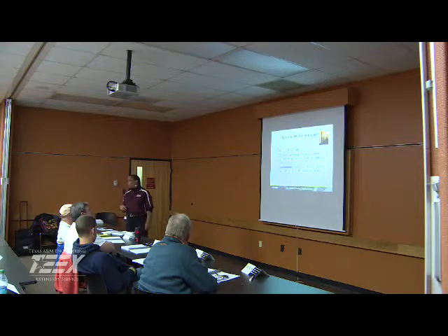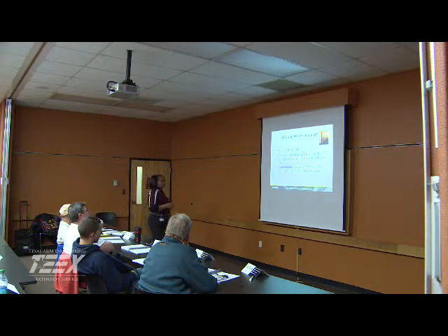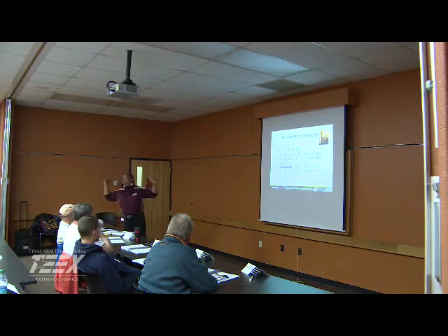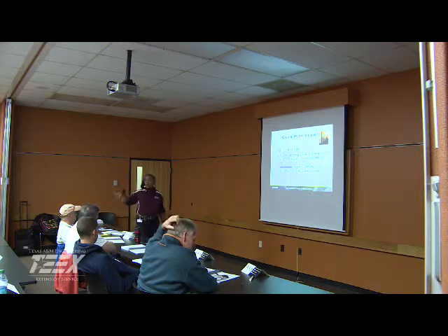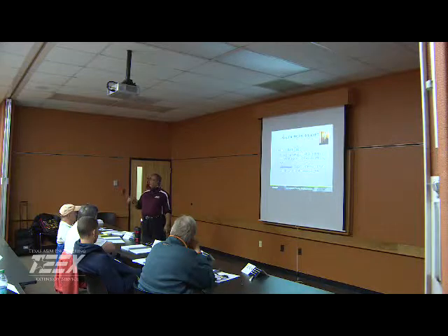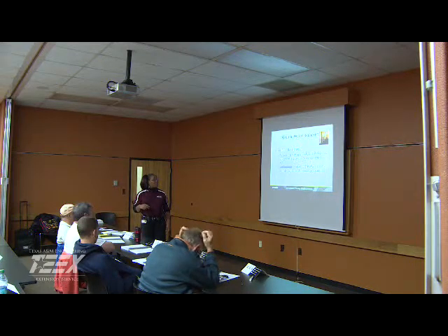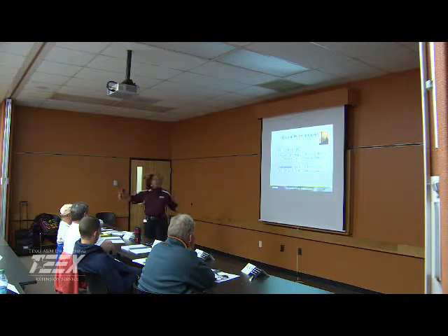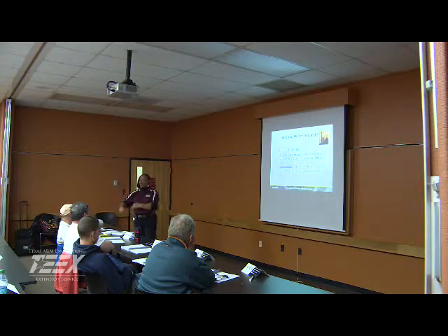So that would be planned artificial recharge. Unintentional would be irrigation or your sewage treatment plant effluents, septic drainage fields, leaking septic systems that get into it. And that's an unofficial way of recharging the groundwater. And of course, it's one way that we don't want to occur because we have very little or no control over the contaminants being put into those groundwater systems that way. Man-made reservoirs. That is the reason why, when we look at the sanitation distance for our wells, sewage treatment plant effluents must be more than 500 feet away. And that's to minimize direct contamination of our groundwater sources.